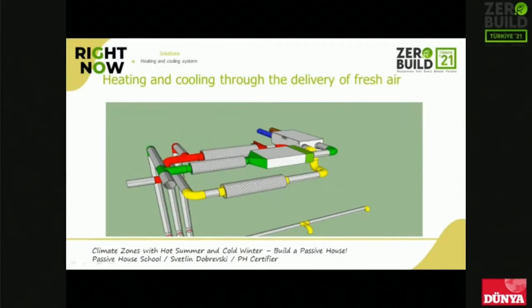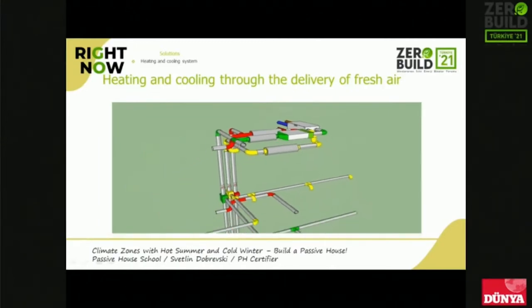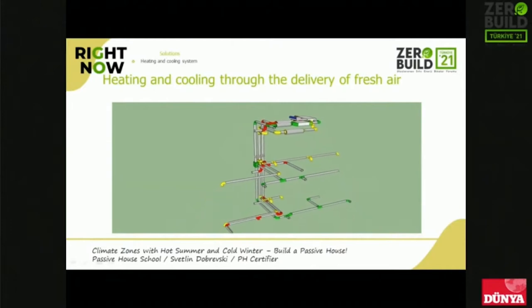The solution came from a properly raised question: what is needed to be able to transfer enough power? More air volume. A different approach was taken under estimation at that time. We decided to add an air-to-air heat pump to the ventilation system with a bigger air volume capacity, and to provide an additional volume of air for the heat pump by adding another branch for recirculation, which is colored in red. We added to the ventilation system another branch of air ducts for recirculation of the inside air. And in order to keep down the speed of the fresh air, we increased the diameter of the fresh air pipes.